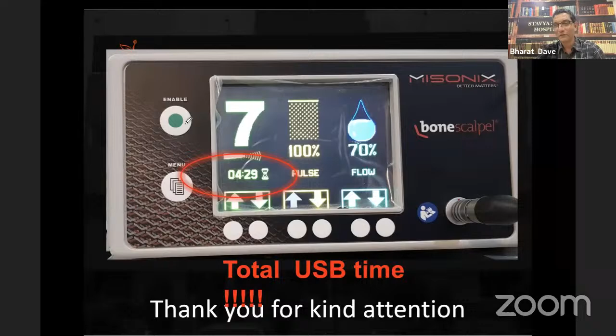This green button enables the console and the handpiece with which you are going to cut. We must charge the whole irrigation tube, which passes from here, in order to have it functioning properly. If it is charged, then water irrigates through that tube. If the water does not come, it will generate a lot of heat and burn the tissue. So make sure that before enabling, we charge the tube and make sure that the water is coming.